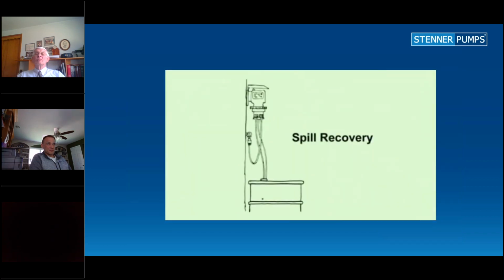To help prevent chemical from collecting in the tube housing, which can cause the rollers and the roller assembly to seize and damage the tube, and to reduce spillage on the floor, a spill recovery can be set up using a section of the 1/4 inch suction discharge tubing inserted into the tube housing cover. The tubing will help drain chemical back to the tank in the event of tube failure.